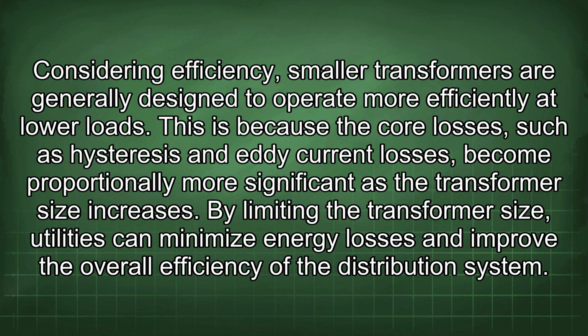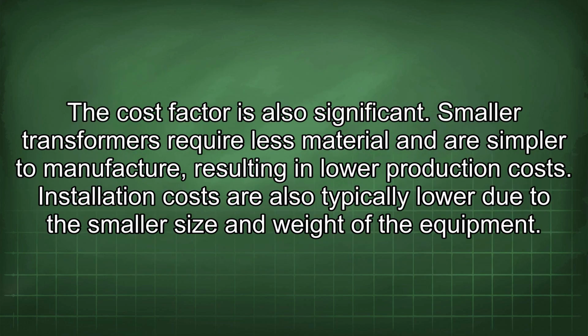This is because the core losses, such as hysteresis and eddy current losses, become proportionally more significant as the transformer size increases. By limiting the transformer size, utilities can minimize energy losses and improve the overall efficiency of the distribution system. The cost factor is also significant. Smaller transformers require less material and are simpler to manufacture, resulting in lower production costs. Installation costs are also typically lower due to the smaller size and weight of the equipment.